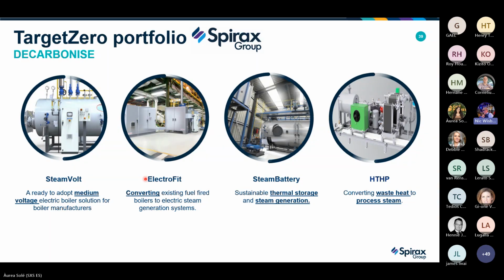So, steam battery. A lot of places are moving more towards, say, solar energy. But the challenge with solar energy is how do you store that energy? Traditionally, the battery packs, the cells required to store that energy, are quite expensive, and they can at times be very difficult to get hold of in the Africa area. What the Steam Battery does is, think of an accumulator with an electrical element. It's filled with water, and we heat the temperature and increase the pressure up to 20, 30 bar, 32, and so on, depending on your system. Then when you need that steam, say you're running a night load which is not high enough to justify turning on the boilers, or you need maintenance on those boilers, we discharge that hot water and, by differential pressure, create steam.